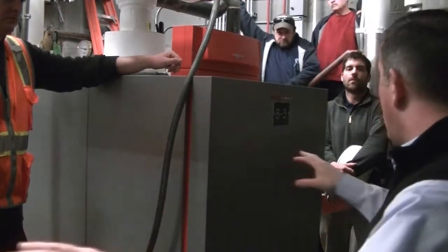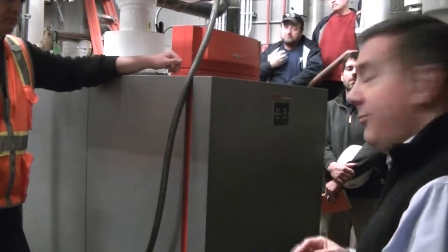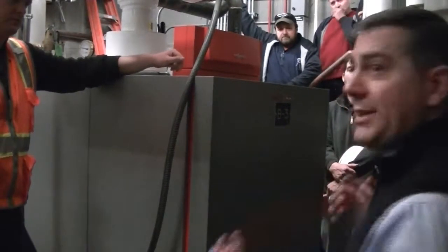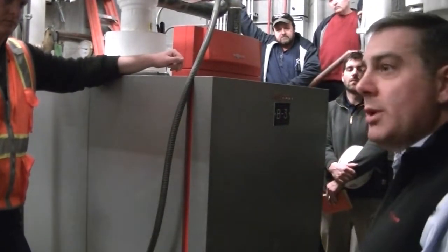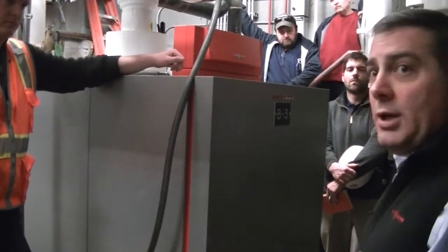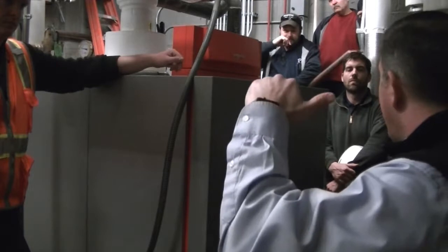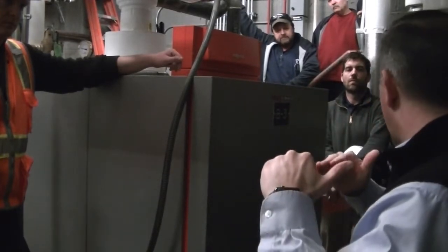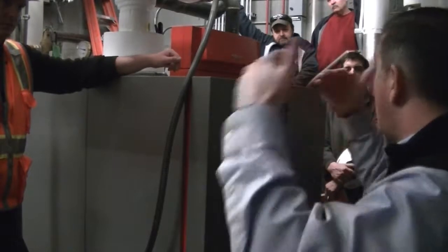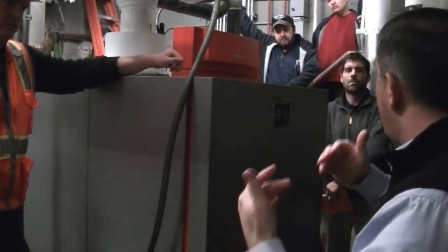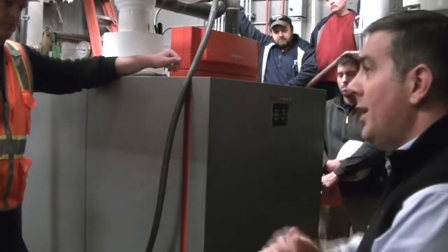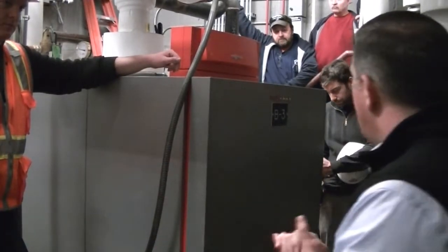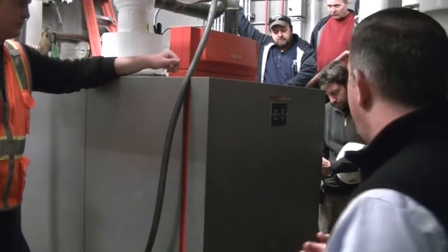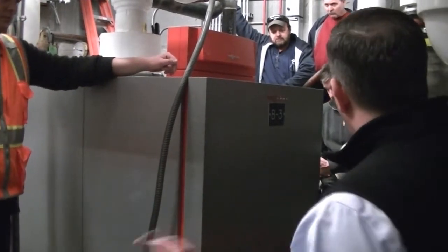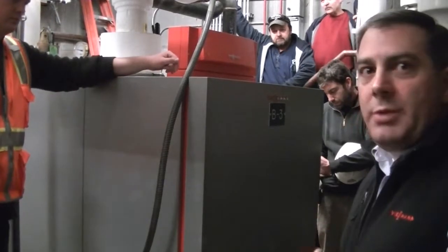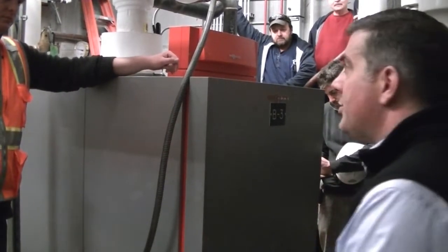So the way that the other 4 boilers will stage and rotate is that if the cogen system is not keeping up with the load and we have to energize the Viessmann system, the lead Viessmann boiler will come on. If it hits 60% of its full input, it'll actually drop down to 30% and then pull on the next boiler, and they'll modulate up and down together. If those 2 boilers hit 60%, both of those drop down to 30% and then pull on the next one, and so on and so forth. And we can do this with our control package up to 8 boilers. So that's the one thing you want to keep in mind. If you come down here on a mild day and you say something's wrong with the system, all of these boilers are running, and it's only 40 degrees outside, that's why. And that's going to be different than what you're used to in a typical stage boiler system.